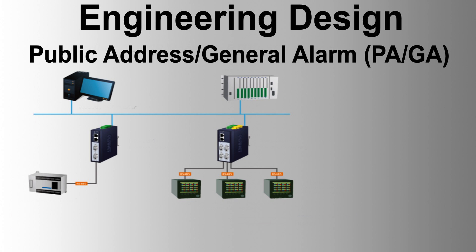PAGA hazardous area classification: equipment selection and installation comply with relevant IEC and IP codes. Equipment ingress protection is rated at least IP 65; indoor environments at least IP 42. Outdoor process areas use explosion-proof sounders and beacons. Hazardous area certification is provided by a notified body compliant with ATEX directive 94/9/EC.